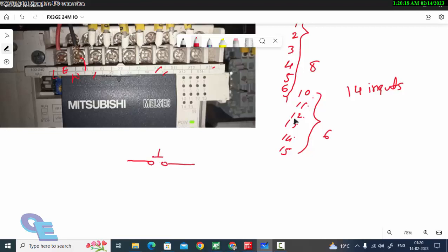Here the S by S terminal is there. If I connect the S by S terminal to one terminal of the input, and connect the other terminal to the positive supply, then the flow of current will be from the field device to the terminal, to the PLC. So this input is acting like a source.